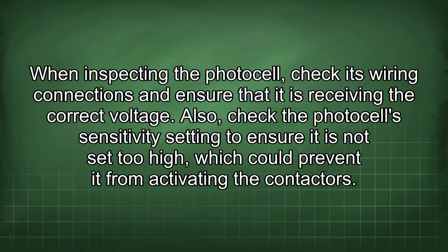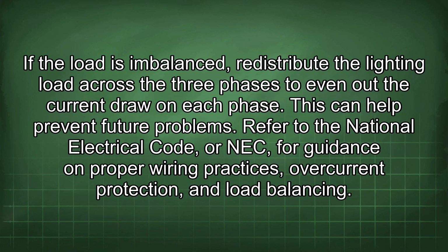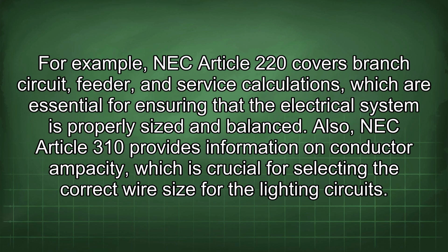If the load is imbalanced, redistribute the lighting load across the 3 phases to even out the current draw on each phase. This can help prevent future problems. Refer to the National Electrical Code, or NEC, for guidance on proper wiring practices, overcurrent protection, and load balancing. For example, NEC Article 220 covers branch circuit, feeder, and service calculations, which are essential for ensuring that the electrical system is properly sized and balanced.